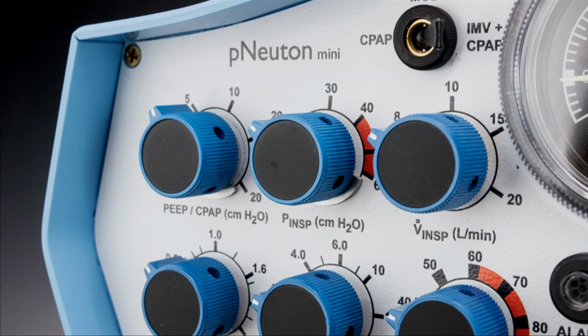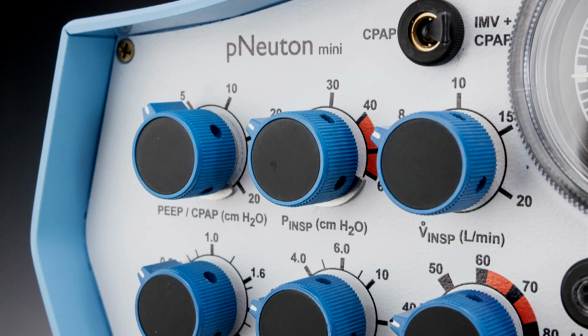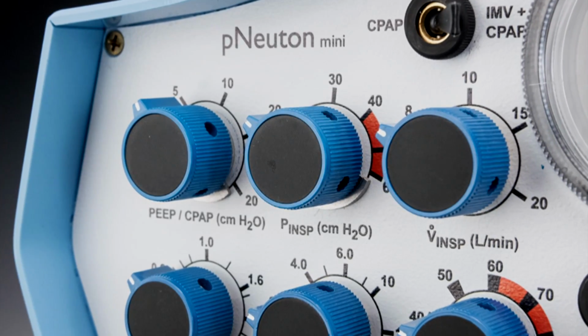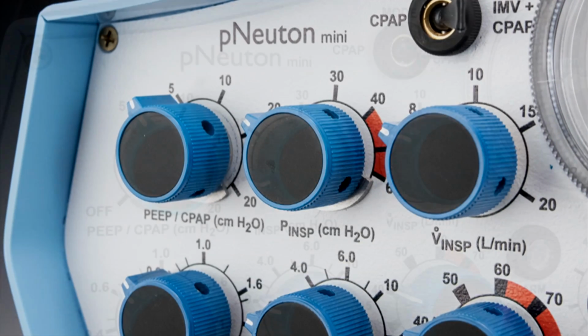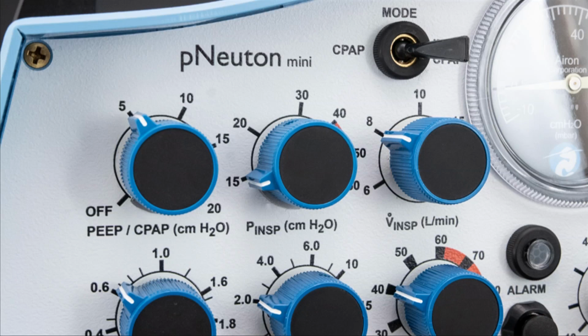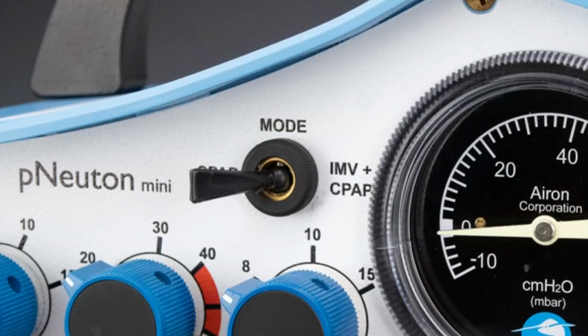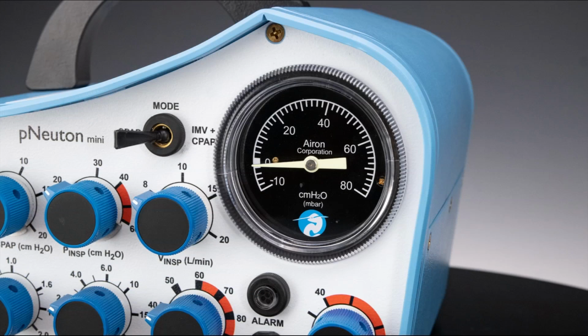Peak pressure control. To the right of the PEEP CPAP control is the PINSP, or peak pressure control for each breath. The inspiratory breath airway pressure can be limited from 15 to 60 centimeters of water and operates only in the IMV plus CPAP, or intermittent mandatory ventilation mode, for pressure-limited ventilation. As a helpful feature of the Mini, the set peak pressure will be visible on the pressure manometer as a visual indicator of pressure delivery for the inspiratory time you desire, and then it will drop to your set PEEP level.